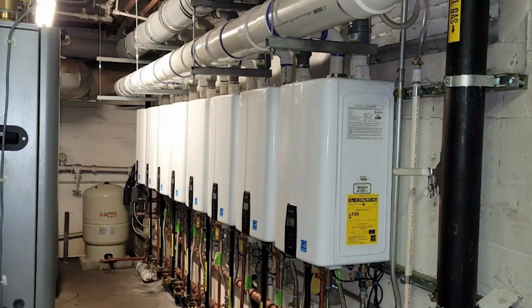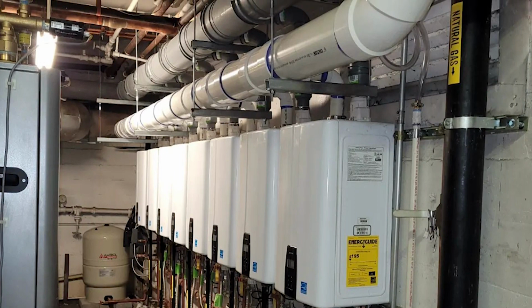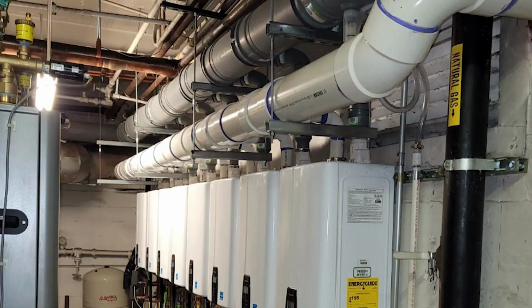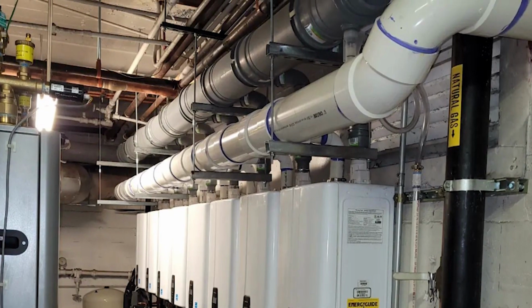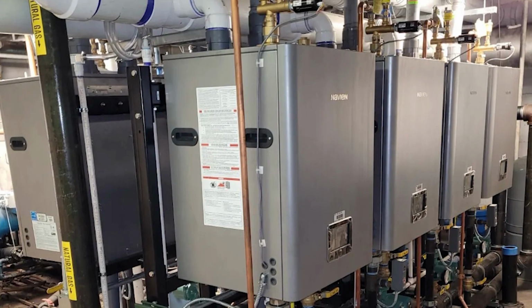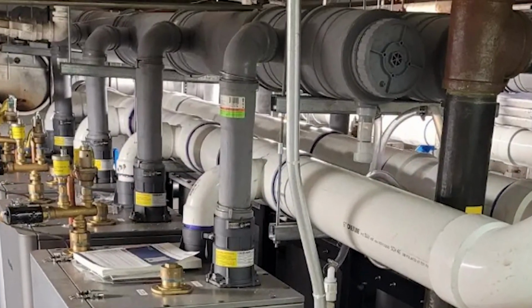It's actually two parts. We're going live here now to Staten Island, where a co-op in the middle of town representing 5 buildings and 60 units is powered by this very mechanical room here. 16 total units. That's 8 boilers and 8 NPE water heaters, both of which are rack mounted. The water heaters are inline, the boilers are back to back, but both are vented with an 8-inch diameter manifold here. So, you know, the large diameter Centrotherm stuff, tethering these all together in a cascade system.